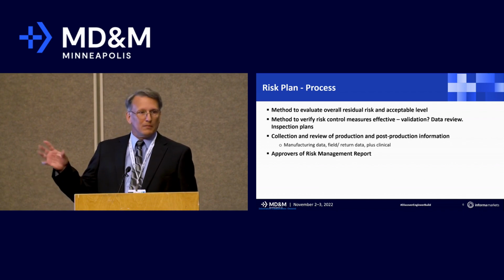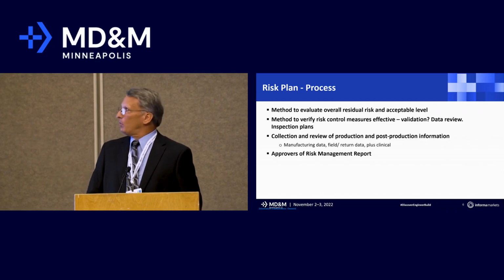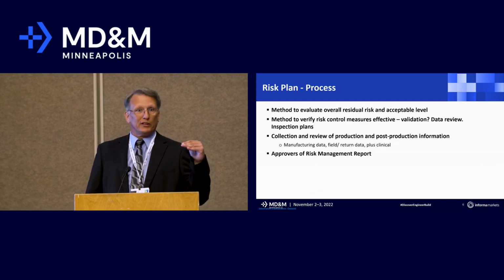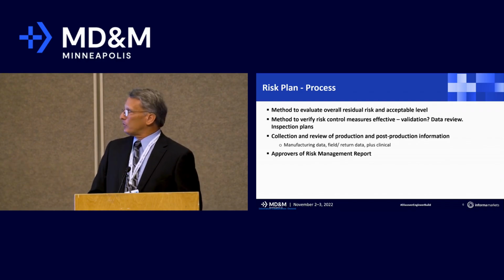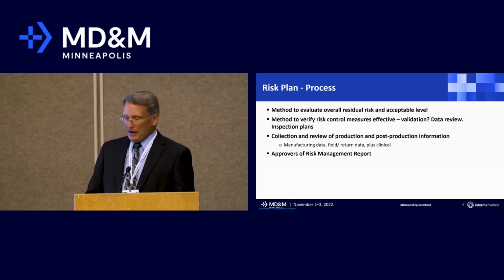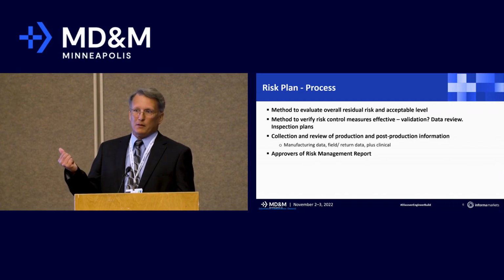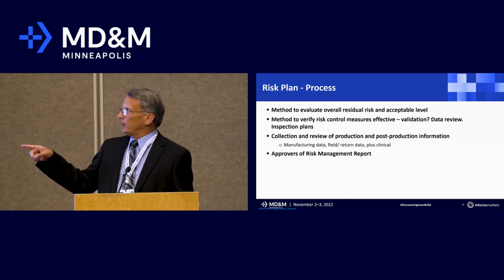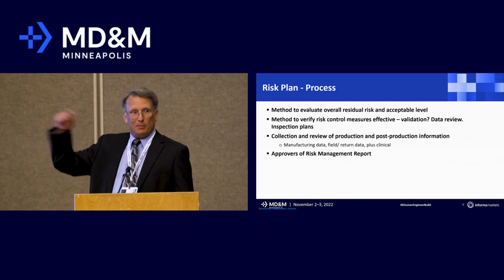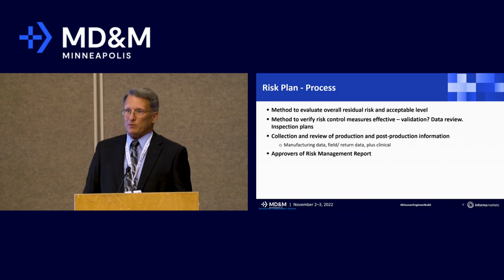So have some, again, up front, understand who's responsible, what data sources are you for sure going to do. Again, you can always do more, but be careful of signing up for too much early. And obviously, I flag in here that the approver of the risk management report is expected in the plan. The main reason I flag it here is a trigger: if they're going to sign it off, they better know what's in the plan, because they have to sign off on a lot more things than they used to be responsible for.